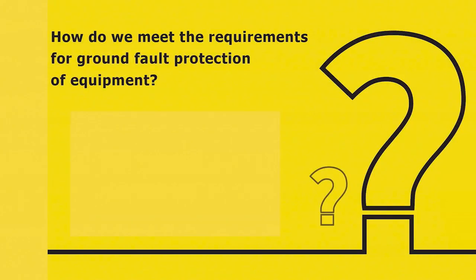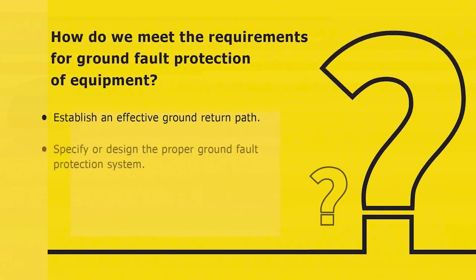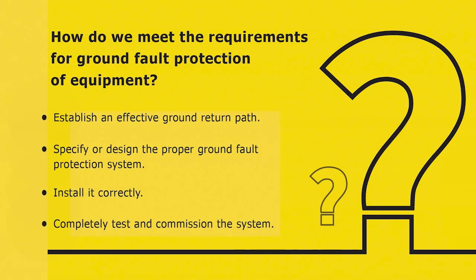So what are we going to do to make sure that we meet the requirements for ground fault protection of equipment? One, we're going to establish an effective ground return path. Also, we're going to specify or design the proper ground fault protection system for the application. We want to supply and install it correctly. And we want to completely test and commission the system to make sure that it works as intended and as designed.